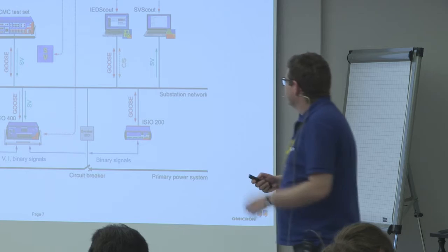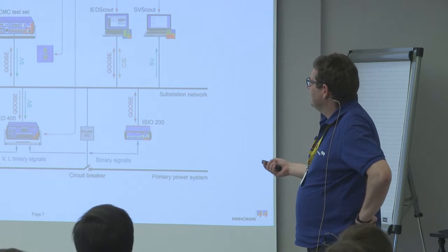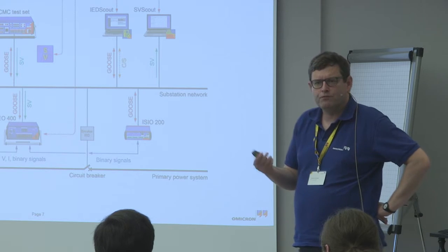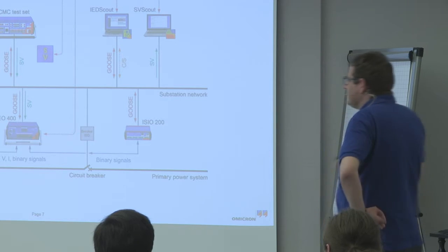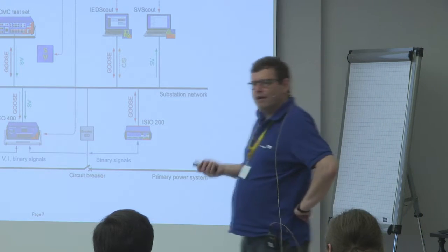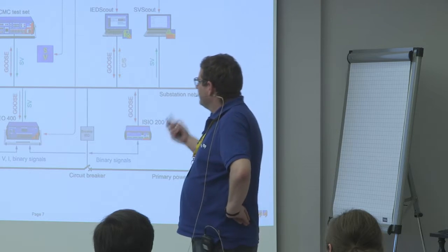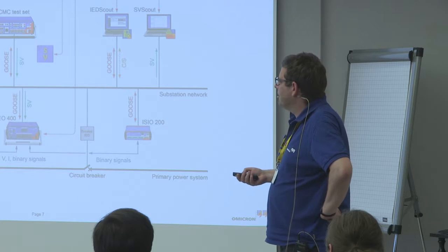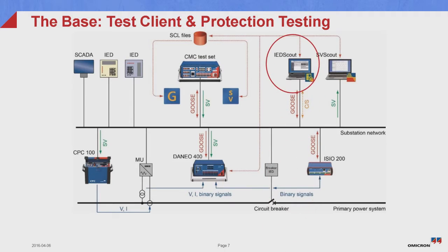So it's quite easy. The other possibility is that, for instance, the SCADA system communicates with the IED for control point to point using TCP/IP. So we really have to work here with different tools. If we want to test this, this means, for instance, if we want to play the SCADA system, I have to establish my own IP connection to the server.